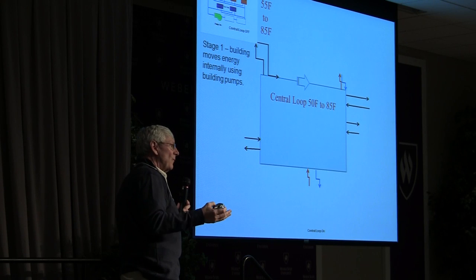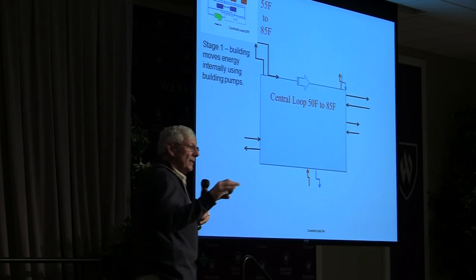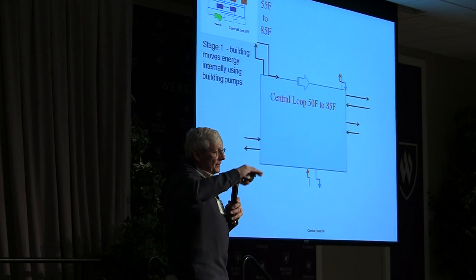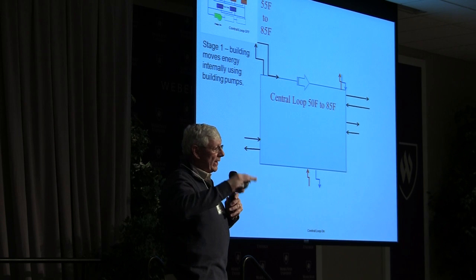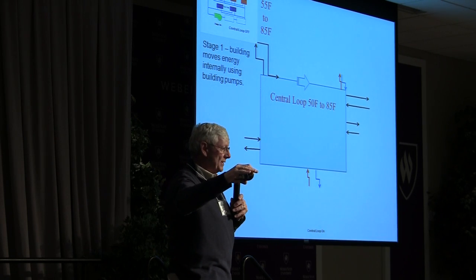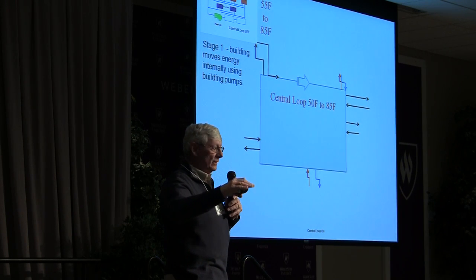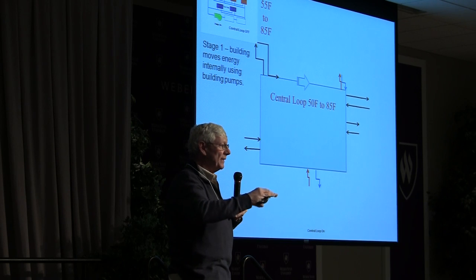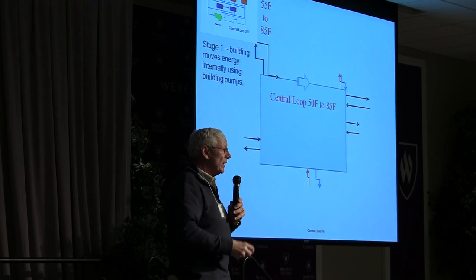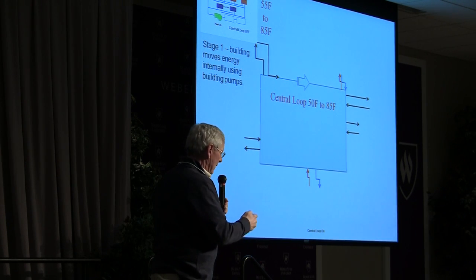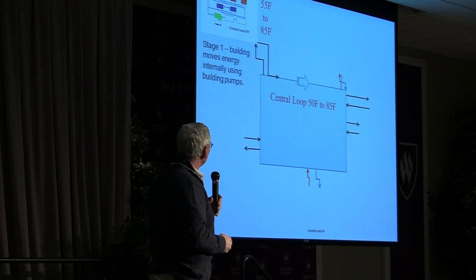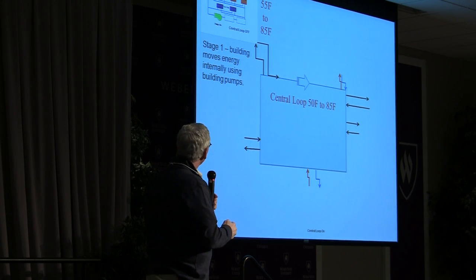There's about 25% more energy available on the cooling side, because to take it to the heating side we can now include the heat of compression as part of our transfer. We can use that within the building, but we can also take it further. So the ratios of what we need become something you really want to look at. That's stage one.